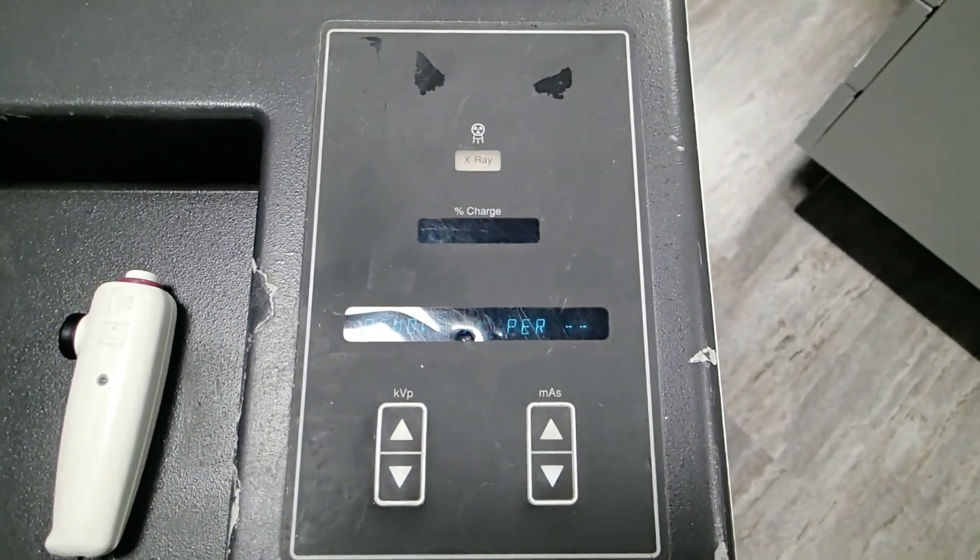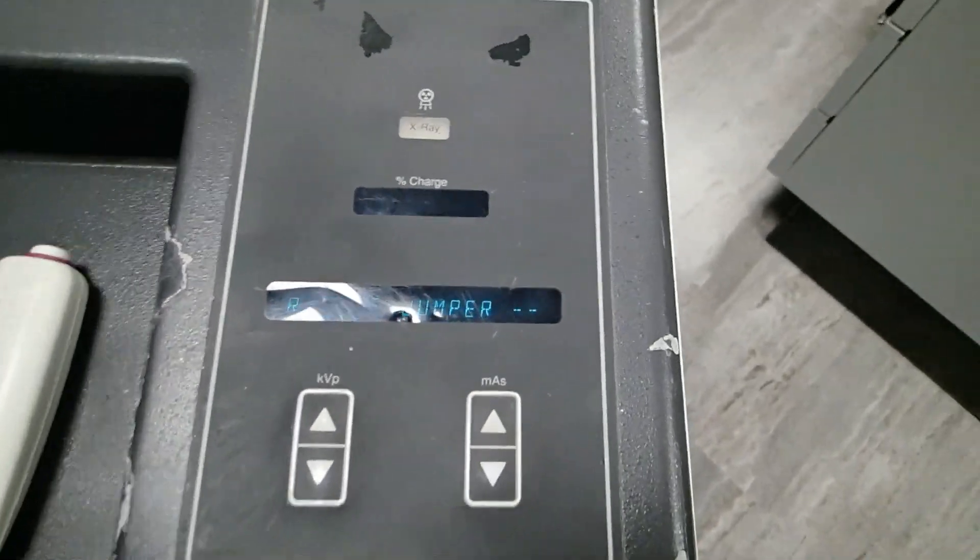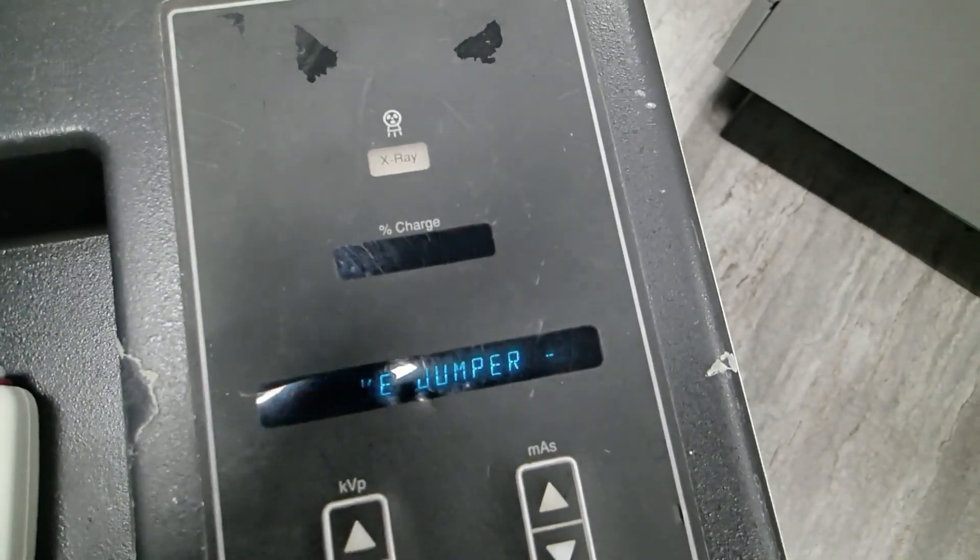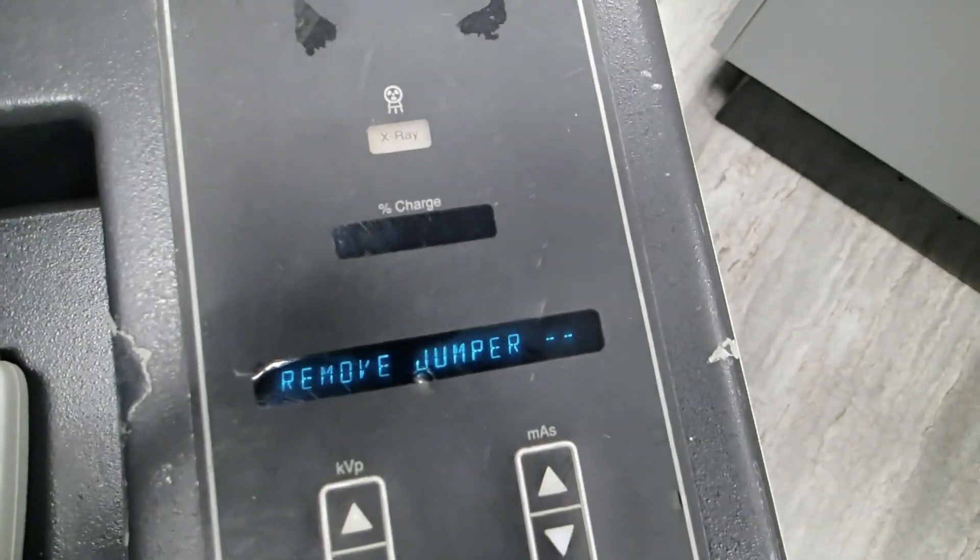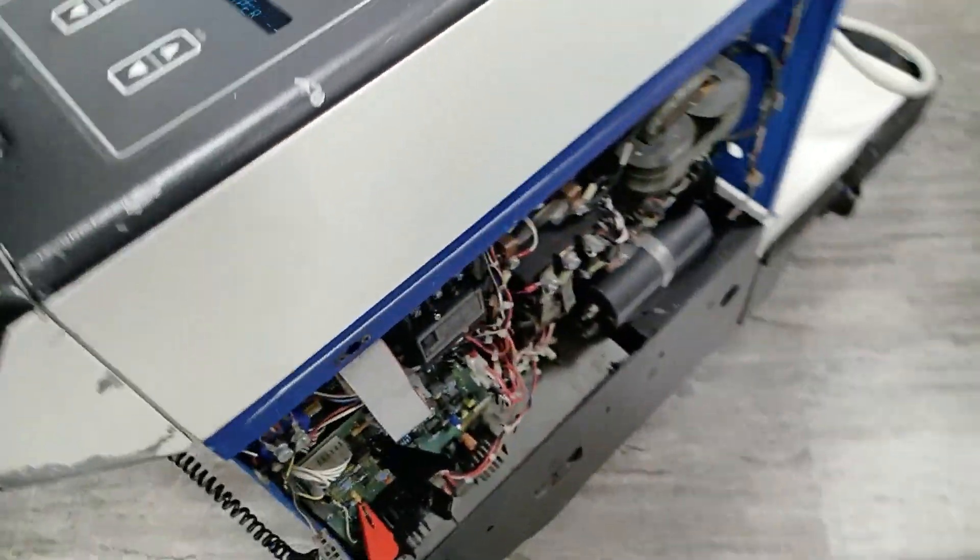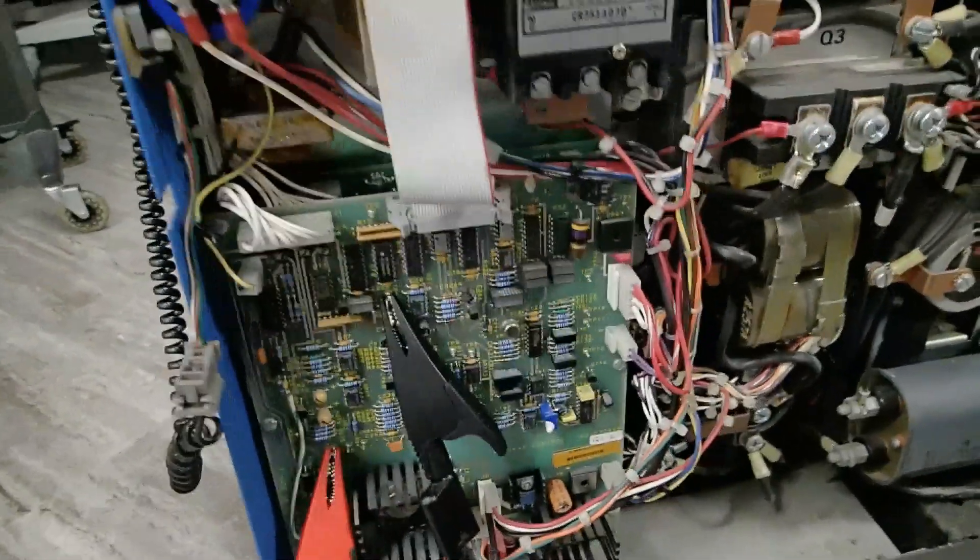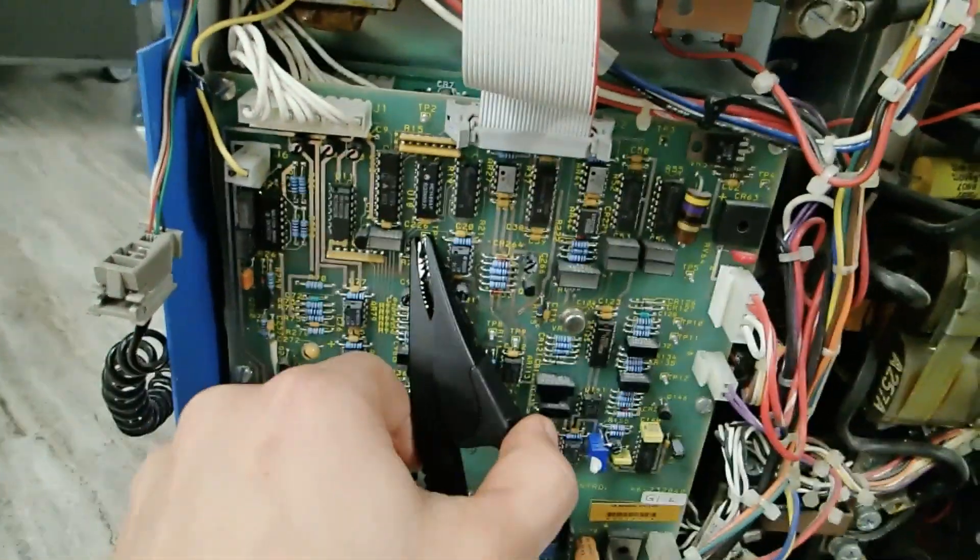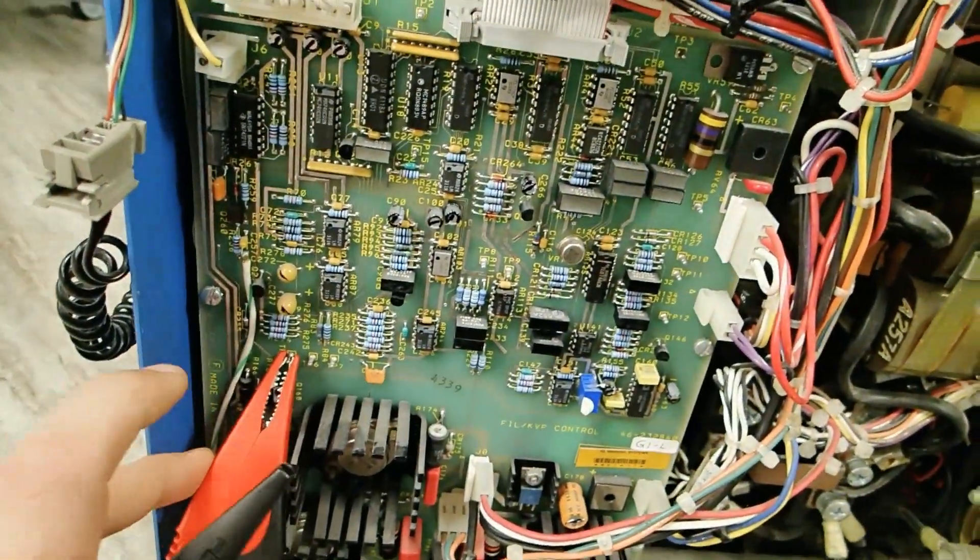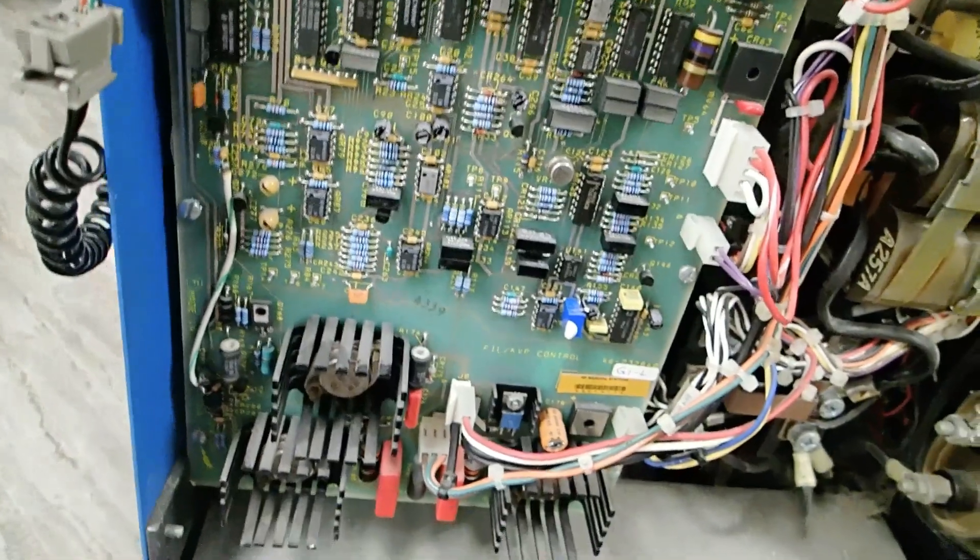At this point, we've gone through all the KVP tests. The device is telling us to remove the jumper. We're going to go down here to our board, making sure to carefully remove our jumper from the test point. Once that's done, we can let the AMX4 know that we've done that.